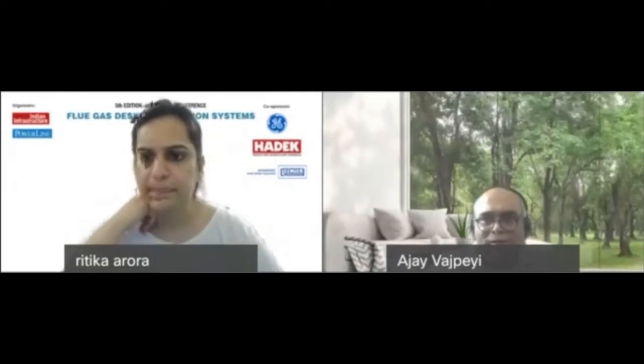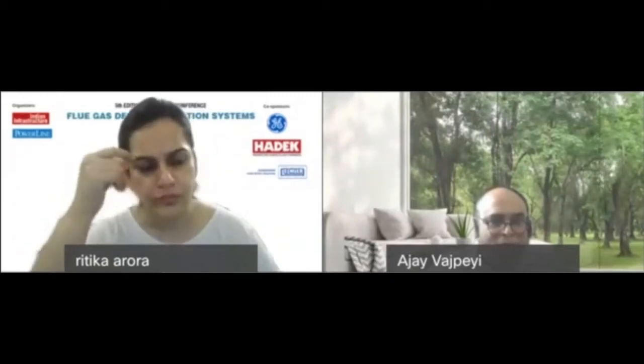Could you throw some light on wet stack liquid collection pipe material of construction inside the flue? There are multiple technologies available, and different materials which are allowed. Those typically have to be corrosion resistant materials, so a choice is available - it could be nickel alloys, titanium, or FRP. Lots of choices are available.